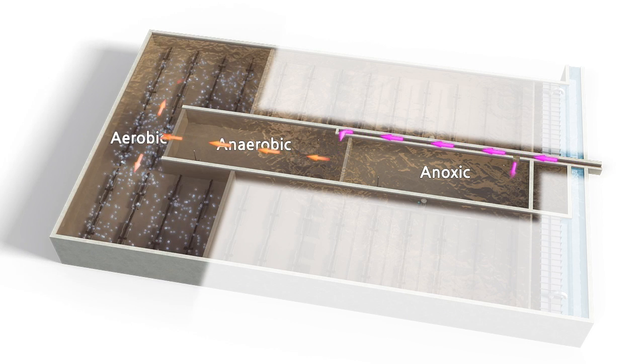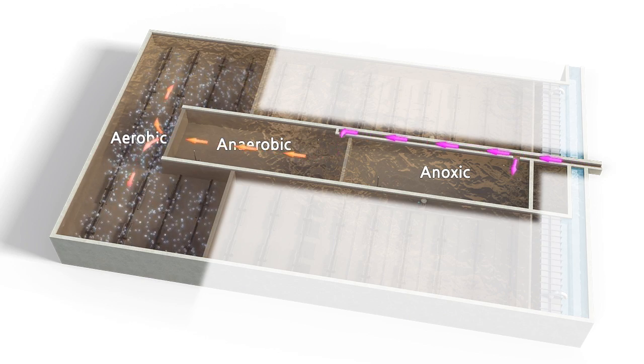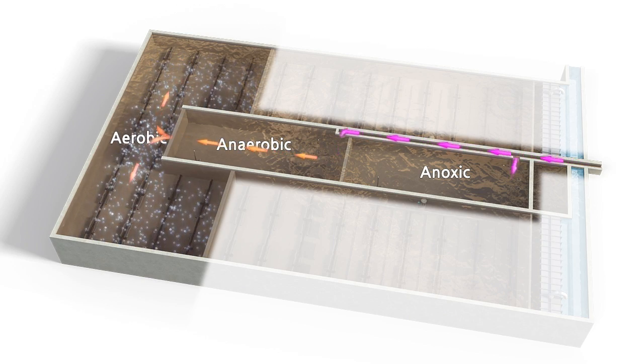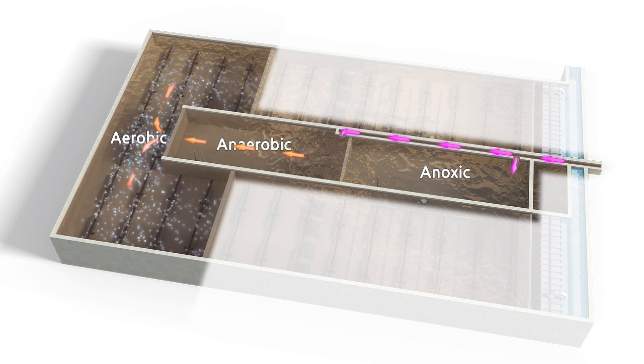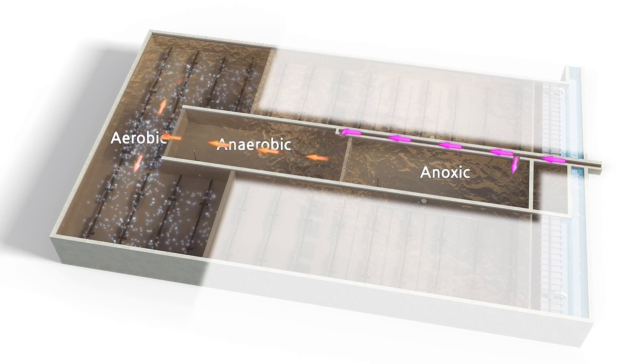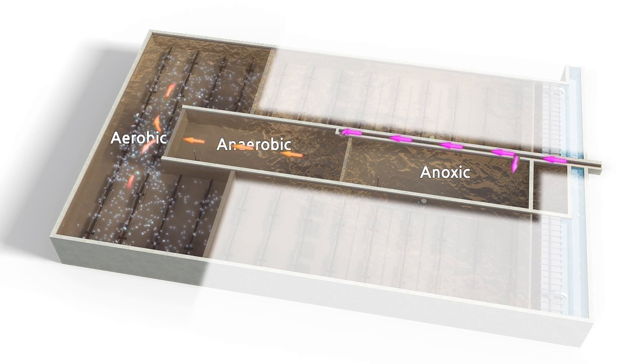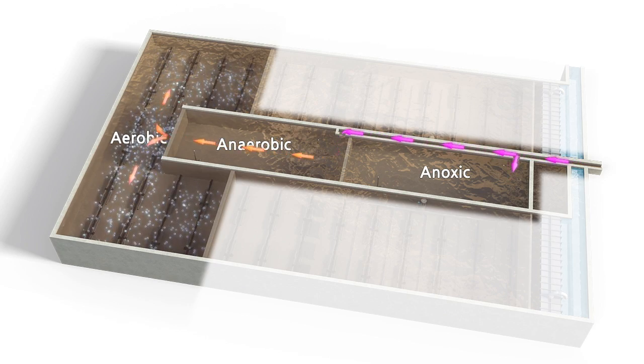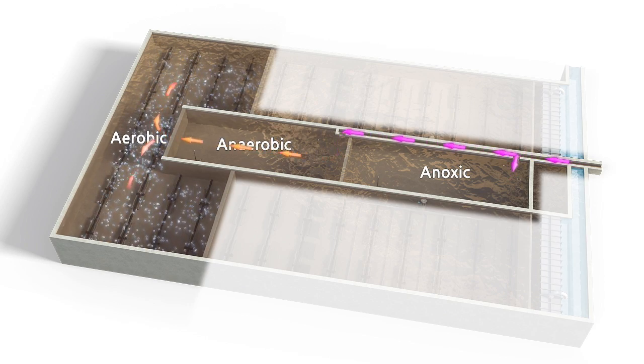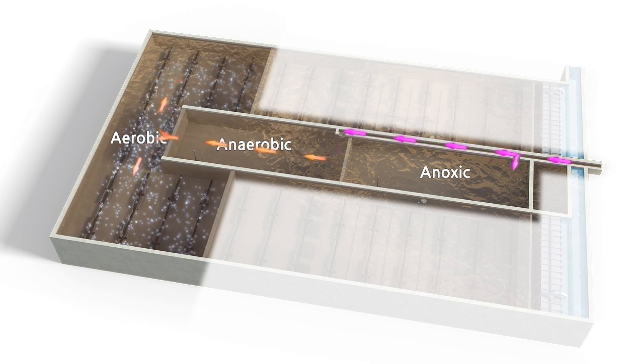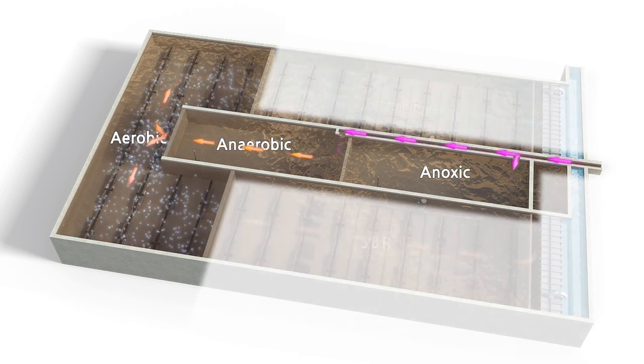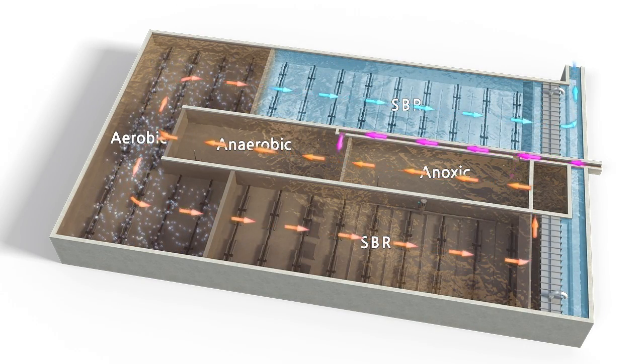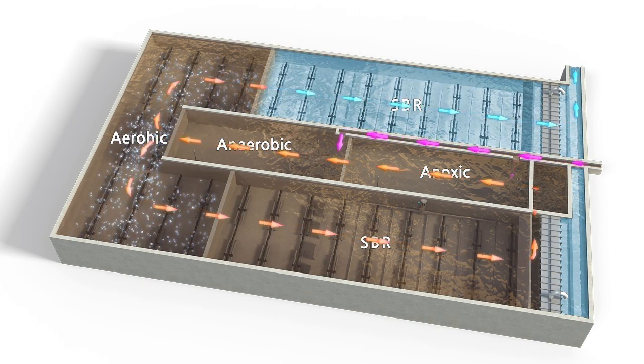In the aerobic cell, the required amount of air is continuously supplied through the uniformly arranged diffusers at the bottom of the cell. The removal of organic matter, nitrification, and also the luxury uptake of released phosphorus from the anaerobic cell take place. The treated water after the aerobic cell then flows to the SBR cells.